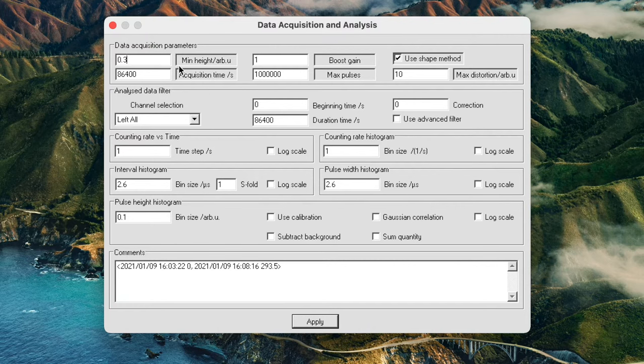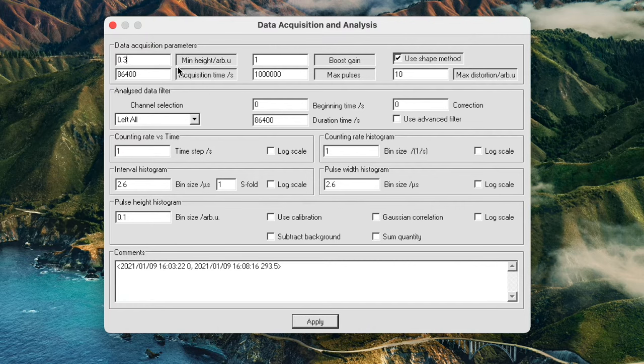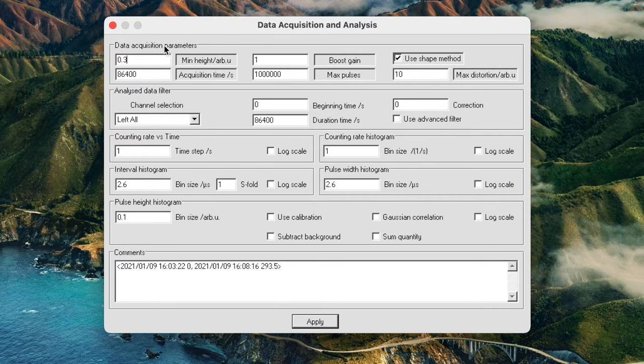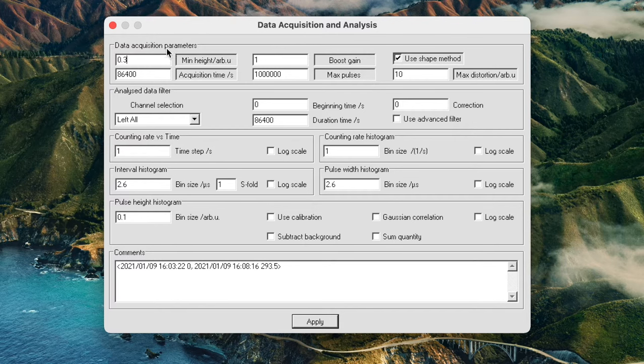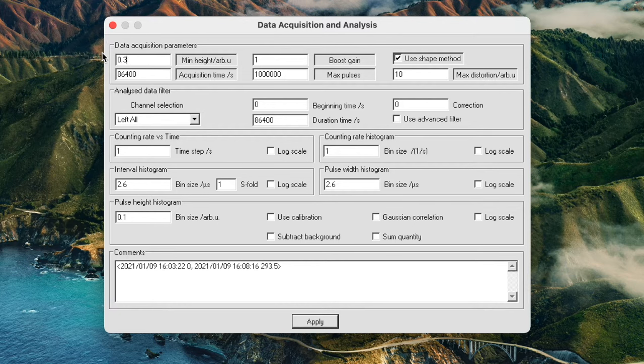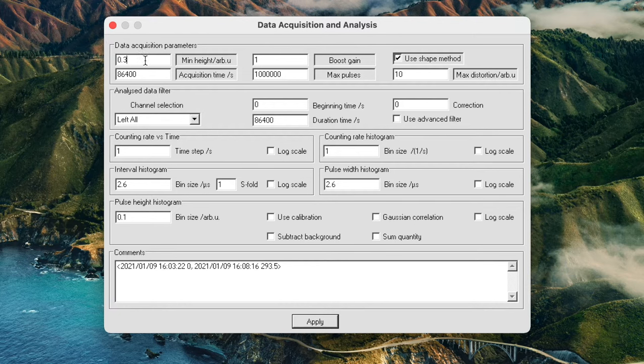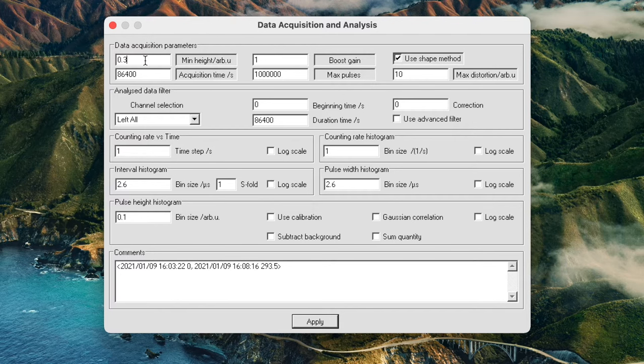The first setting we come to here is the pulse height threshold. This basically discriminates pulses under a certain pulse height. By default I recommend setting this to around 0.3 which is enough to discriminate any electronic noise coming from the spectrometer so that we mainly focus on catching the actual pulses that come from gamma and x-rays. One thing to note is if your detector or spectrometer setup happens to produce a negative pulse, this number needs to be set to a negative number, but with the GSUSB Pro the pulse is always positive.